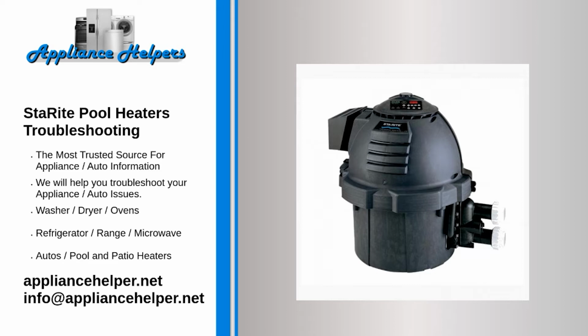The heat pump has a poor water flow. One of the most important ways to keep your heat pump running strong is to ensure that steady water flow is being pushed through the unit. Once the pump loses steady water flow, it will have issues and take a lot longer to complete a heating cycle. Note: only run your heat pump when it has water flowing from the filtration system. No water in a running heat pump may cause irreparable damage.